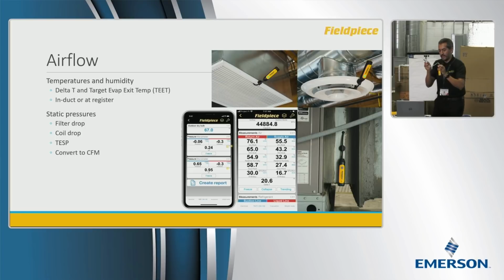But the more important thing is that you are parallel to the airflow. That's a simple way to take a static pressure. Oh, and extremely important, before you enter it into the ductwork, what should you do? Zero it, right? With the JobLink probes, it's pretty simple. Once you power it on, you just tap the power button once, it blinks blue, and that's zeroed it for you. So it's ready to be inserted into the ductwork, and switch on the back P1 and P2 so the app knows where to map the value automatically into your application.